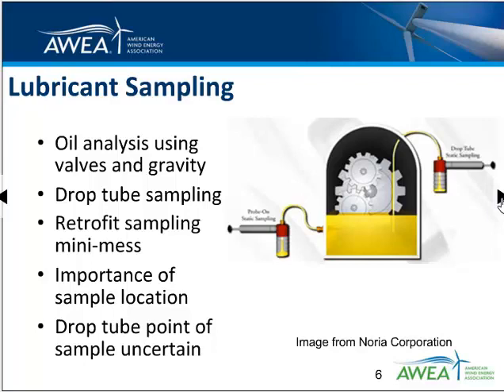Thank you, Bruce. Grease certainly lags oil when it comes to sampling and analysis. Oil analysis, which may be applied in wind turbines to perhaps the main gearbox, is achieved usually using valves and gravity to allow the oil to flow out of the reservoir. Sometimes folks use drop tube sampling, where a tube is inserted at the top and oil is extracted using a vacuum pump. Sometimes machines are retrofitted with a mini mess or sampling valve that allows a more consistent sample location.